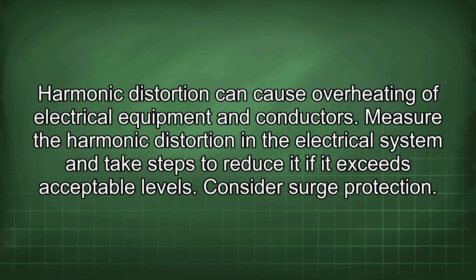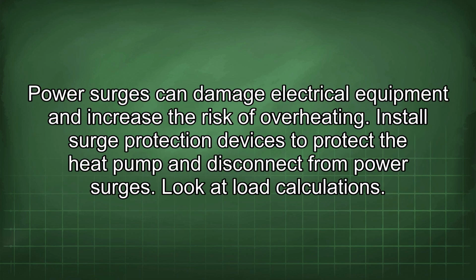Harmonic distortion can cause overheating of electrical equipment and conductors. Measure the harmonic distortion in the electrical system and take steps to reduce it if it exceeds acceptable levels. Consider surge protection. Power surges can damage electrical equipment and increase the risk of overheating. Install surge protection devices to protect the heat pump and disconnect from power surges.